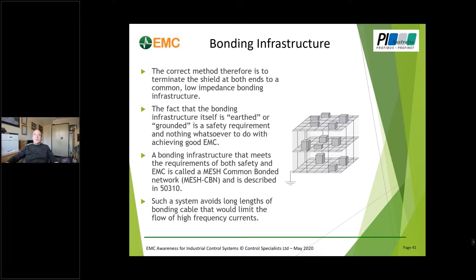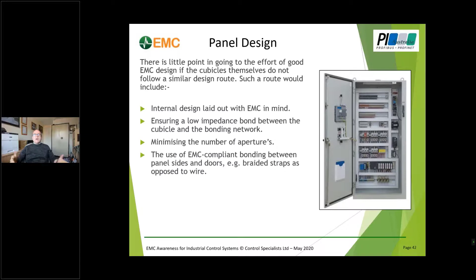There's little point going to the effort of this if the panels themselves don't meet the requirements. So we want them laid out with EMC in mind, ensuring a low impedance bond between the cubicle and the network, which doesn't mean a length of cable - we're talking about using straps, braided straps, etc. Minimizing the number of apertures, which is a strange thing, and using EMC compliant bonding between the sides.